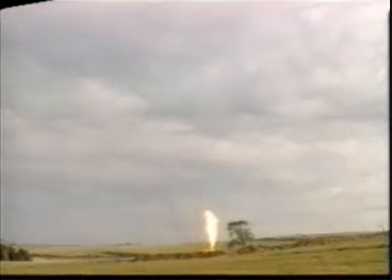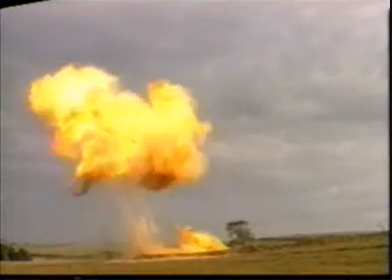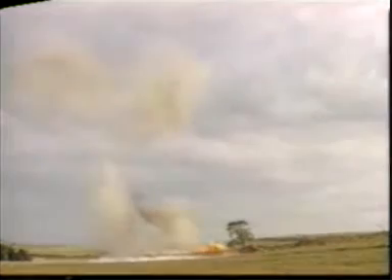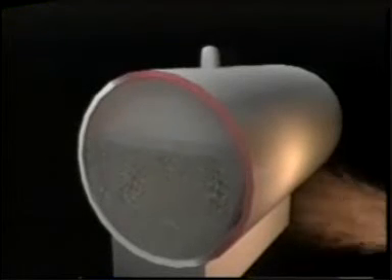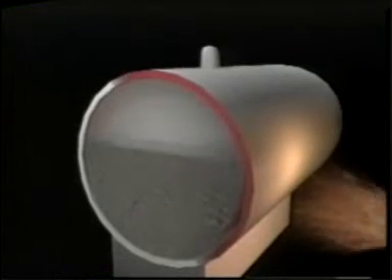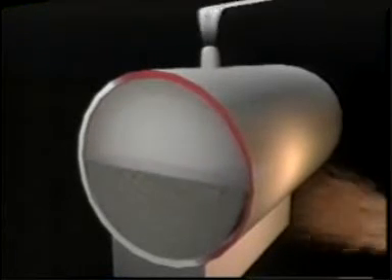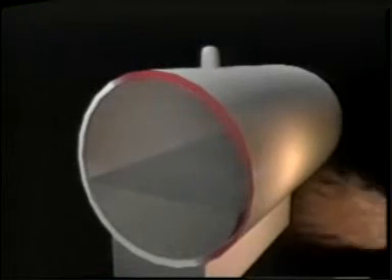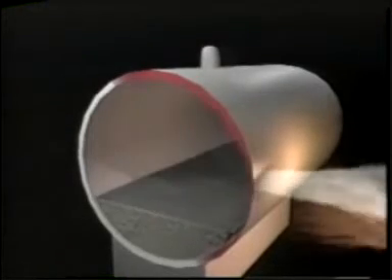Is the situation under control if the pressure relief valve is releasing gas? No. Liquefied gas tanks can and do fail, even when the PRV is trying to relieve excess pressure. PRVs don't prevent the tank from weakening with heat. In fact, by lowering the liquid level in the tank, they can contribute to the weakening of the steel. PRVs releasing pressure do warn us that something is happening. However, with severe fire exposure, a BLEVE can occur whether the PRV is open, closed, or cycling.